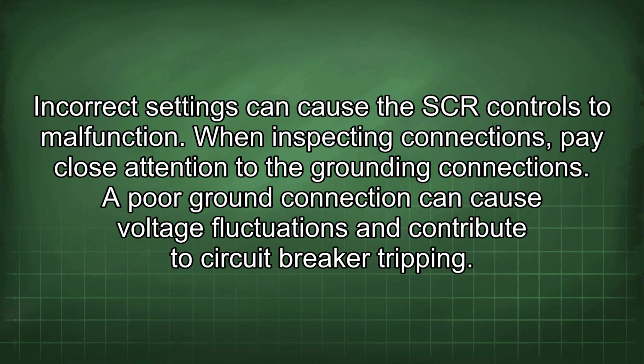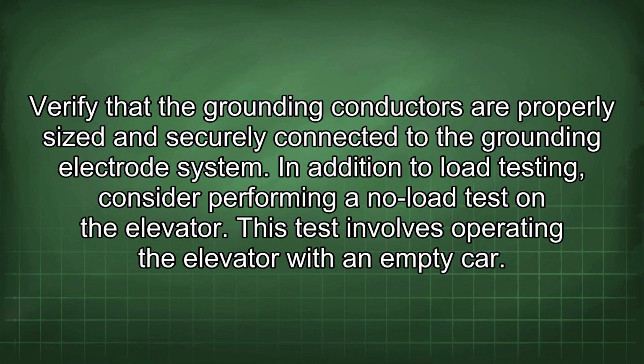When inspecting connections, pay close attention to the grounding connections. A poor ground connection can cause voltage fluctuations and contribute to circuit breaker tripping. Verify that the grounding conductors are properly sized and securely connected to the grounding electrode system.